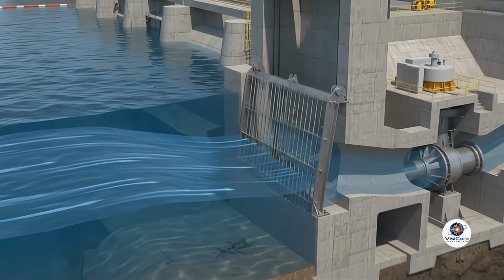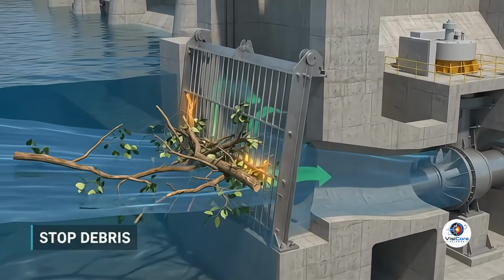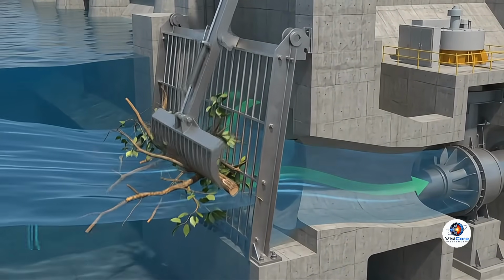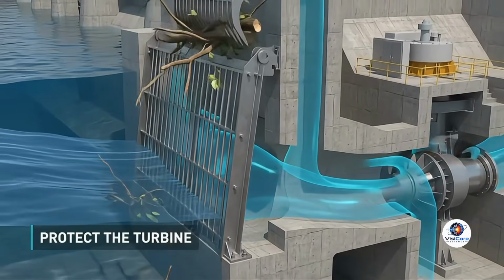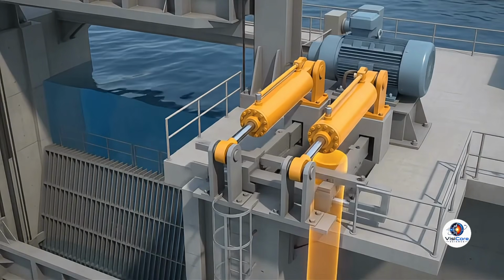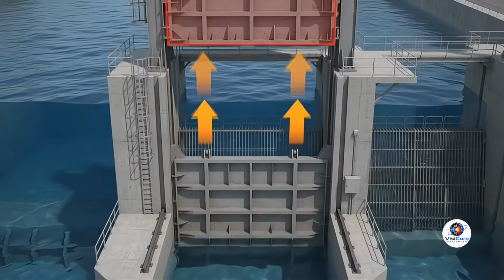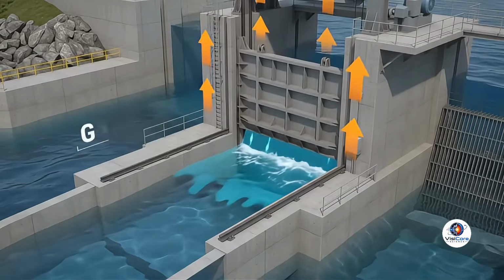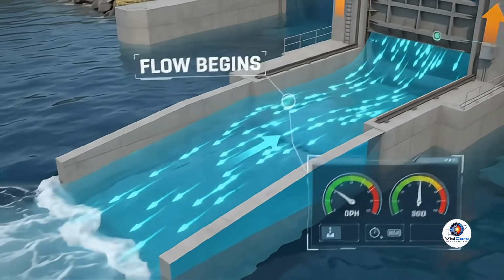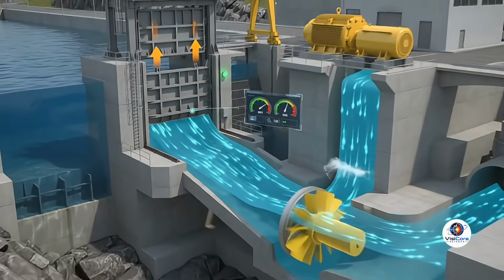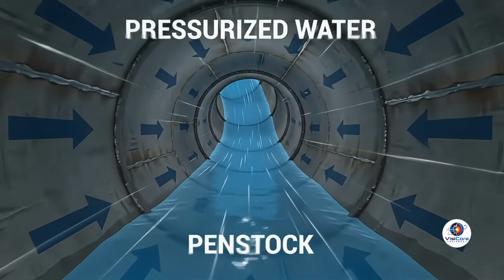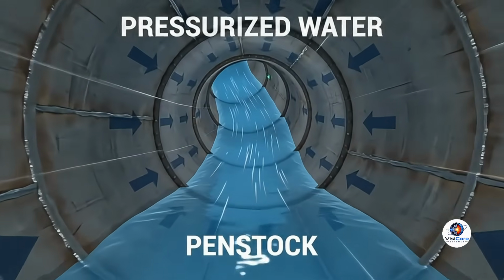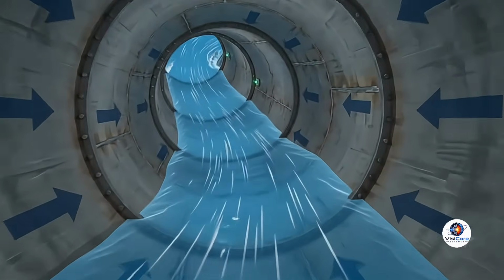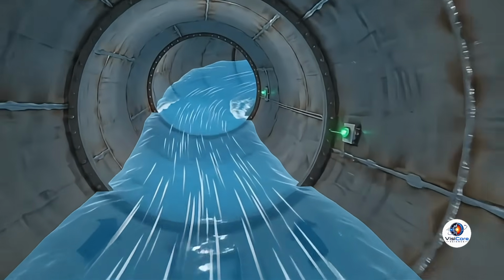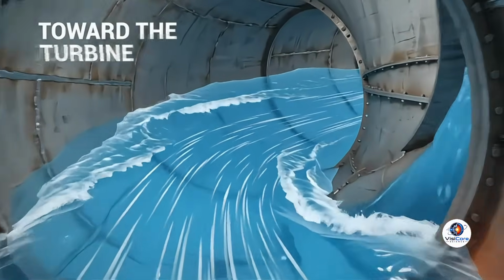The intake admits water, while a heavy steel rack blocks large debris that could damage or obstruct the turbine's internal passages. When generation is requested, hydraulic actuators raise the intake gate. Water begins entering the pressure conduit in a carefully controlled flow. Gravity drives the water through the penstock. The elevation difference creates pressure, while the conduit delivers the flow toward the turbine.